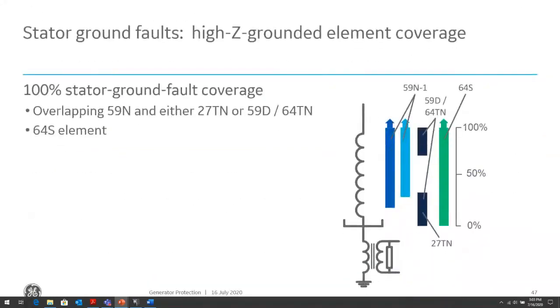So in conclusion, with all those various techniques for determining a ground fault in a high impedance grounded generator, basically what we're looking for is a combination of these various methods that will give us good 100% coverage for ground faults on the stator winding. So it's usually a combination of the 59N and the 27TN, or the 59N and the 59D/64TN.